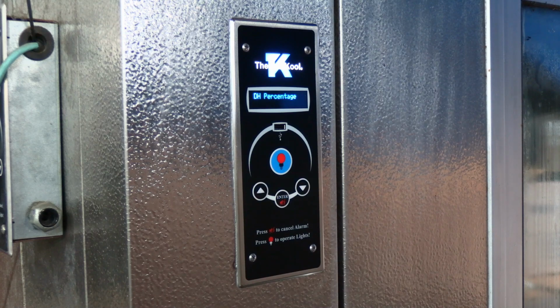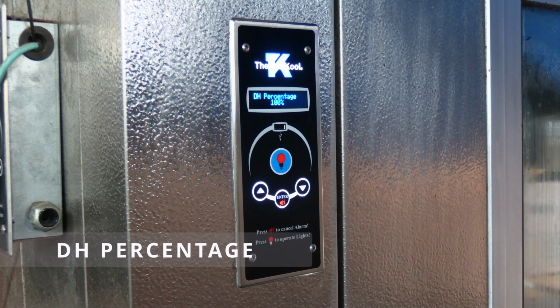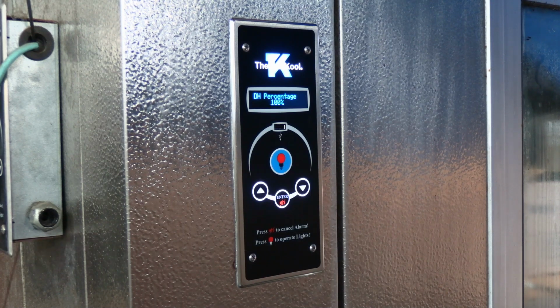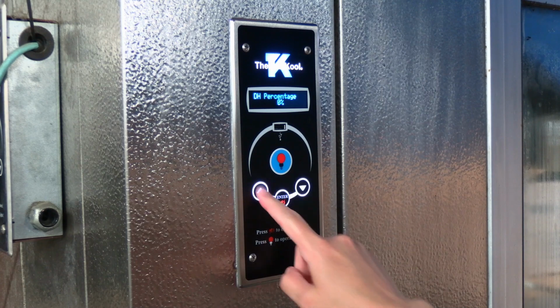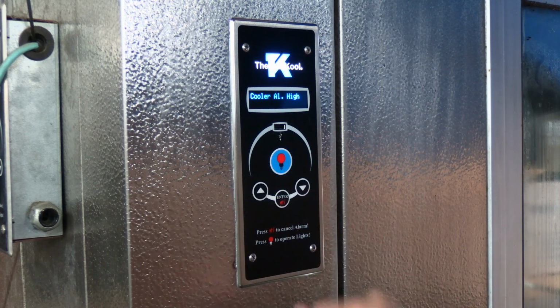The display will show, DH percentage. This option allows you to select what percentage of the 10-minute cycle the door heater will remain on, meaning, if 50% is entered, the door heater will remain on for 5 minutes of the allotted 10 minutes. The default range is from 0% to 100%. To change the percentage, press the up or down arrow, then press Enter.